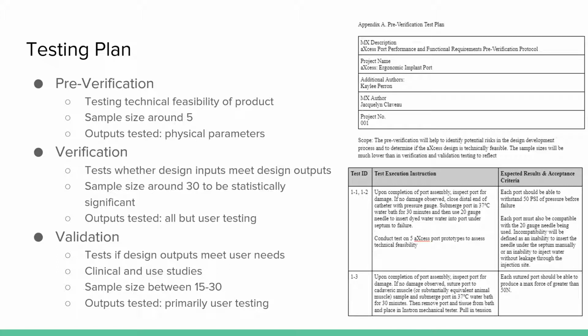From here, we'd roll into a verification plan, which would test whether the design inputs meet our specified design outputs. The sample size for this would be around 30 to be statistically significant in our results, and almost all of the outputs would be tested with the exception of user testing because this wouldn't be in a production scale setting. Finally, we would complete validation testing on production scale models to determine if the design outputs meet the user needs.